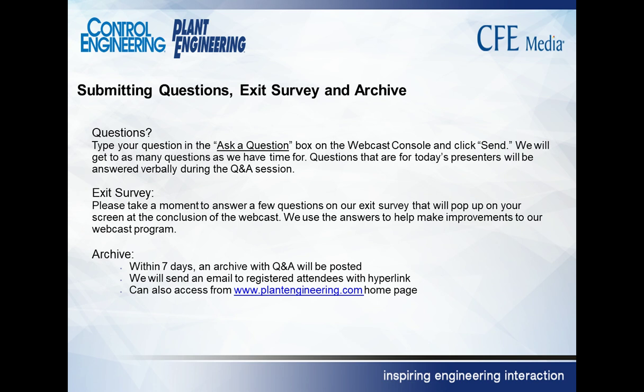Literally, whatever controls the valve, for instance, that you might be throttling the discharge with, typically, if it's an automatic system, is controlled by a motor-operated valve. So you're starting and stopping a motor as that motor runs that valve up or down or closes it. It's not an instant response. The speed response from a motor that's set up properly, from a variable speed drive, can be just as responsive and in some cases more responsive.